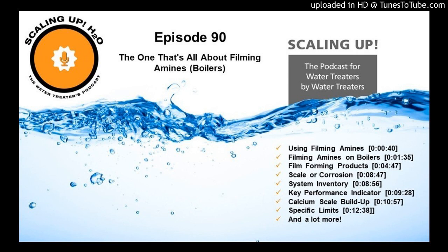So blow it down and start at half. If it's an extraordinarily messy system, I would say even cut it in a fourth. So I'd say maybe start at 250 parts per million, if our 1,000 parts per million scenario is still holding, right? Start at 250.